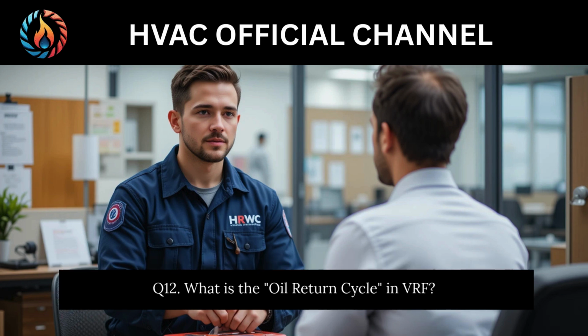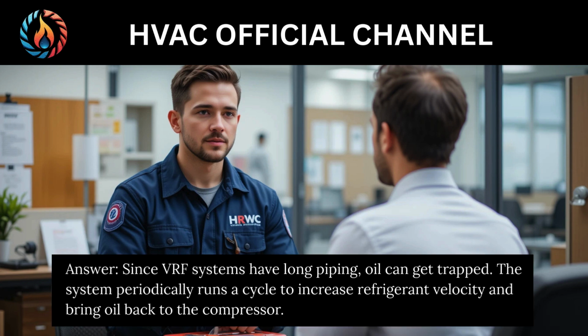Q12. What is the oil return cycle in VRF? Answer. Since VRF systems have long piping, oil can get trapped. The system periodically runs a cycle to increase refrigerant velocity and bring oil back to the compressor.